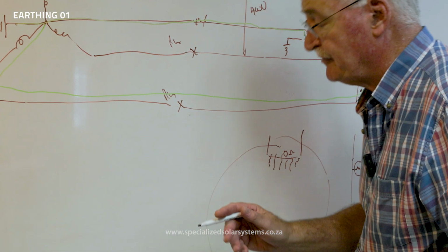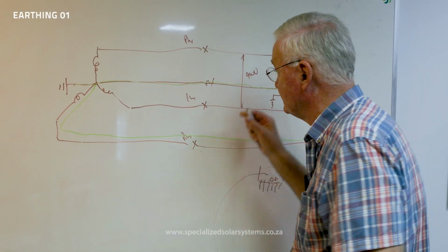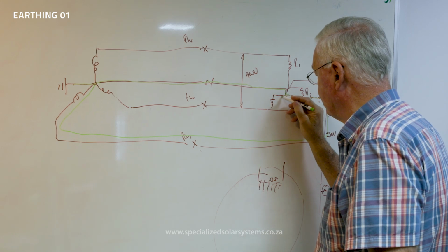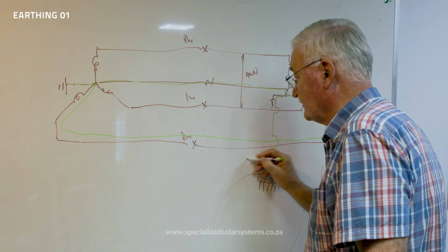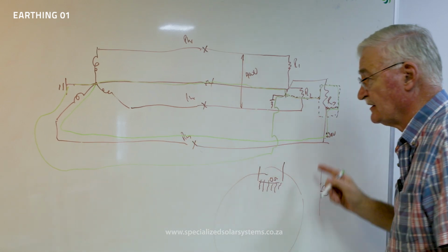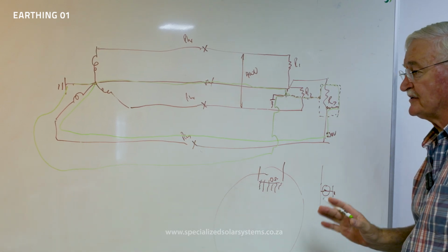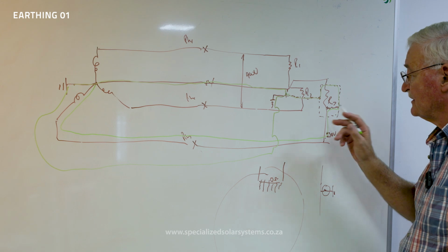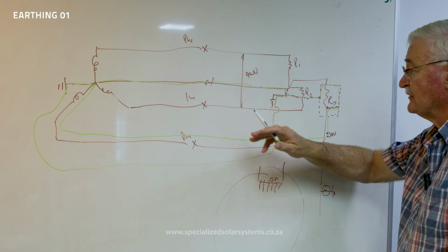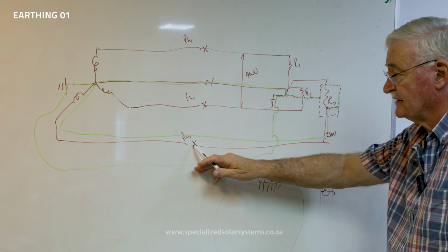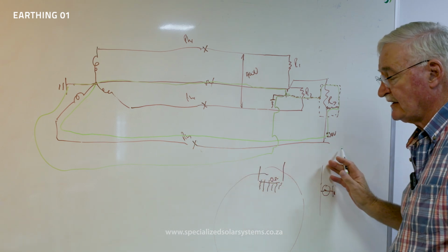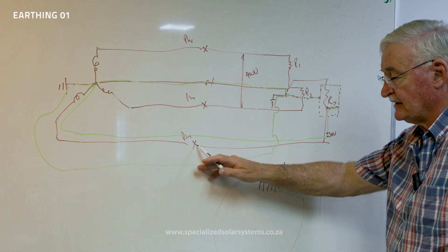So if you look at another circuit here, instead of it flowing through that neutral, if you've earthed it here, you'll also have a path through here, all the way back to this earth over here. So now you can see you have a continuous circuit. You can't have current flowing unless you have a continuous circuit. So with this earth, this breaker will now see the current, okay? Because that breaker there is in series with that supply. So this breaker will pick up that current. And if the current is very high, it will trip.